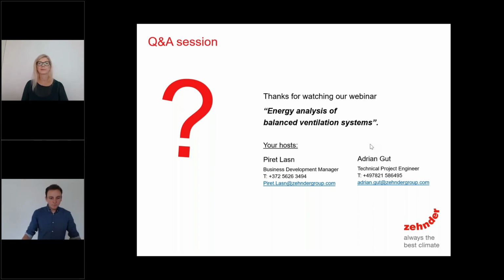Yeah, there's a question. When the unit senses high indoor humidity, is this in the default settings or is this an advanced setting? So, as I already mentioned, we have these integrated sensors measuring the humidity, and if they recognize the humidity is too high inside, the unit will raise the air volume flow. But this is an optional setting that you need to set during commissioning. That's not standard, but it is possible to do it. And we also have external humidity sensors, which can be installed, for example, in the bathroom. And if that bathroom sensor detects high humidity, the unit will also increase the air volume flow.